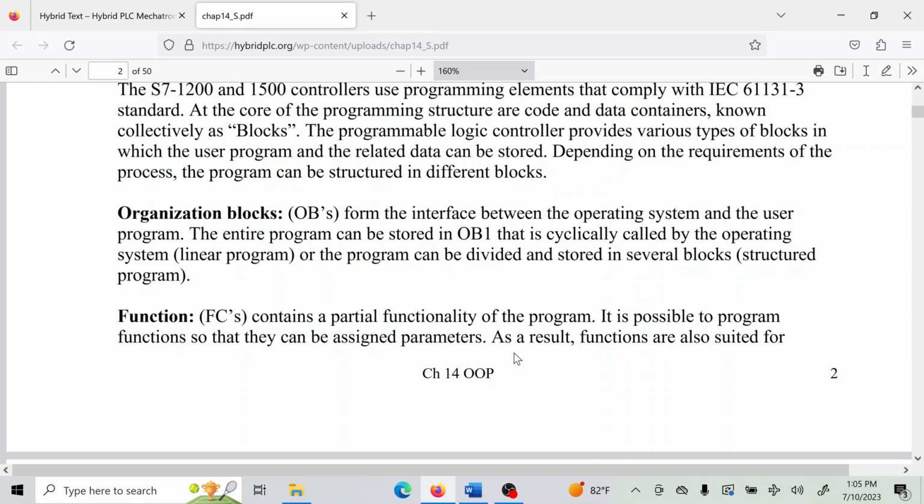We'll create some OBs that are cyclical, timed interrupt, cyclical interrupt programs that come in on a clock and execute, and then are done. So when they are done, they're off, and then OB1 comes back and runs for a little while. So again, OB1 is not a timed interrupt or timed program, but it does carry the ball for most of the time.